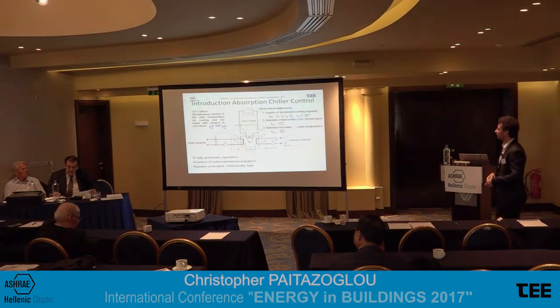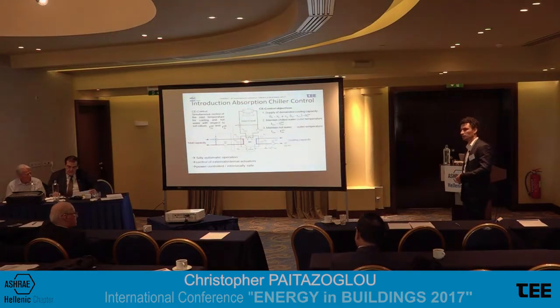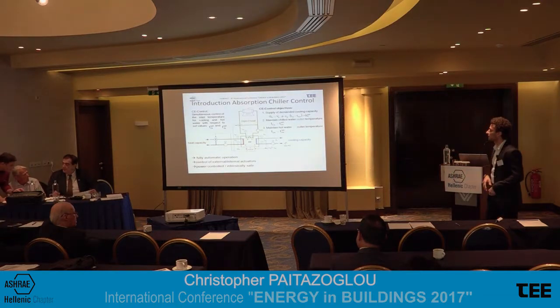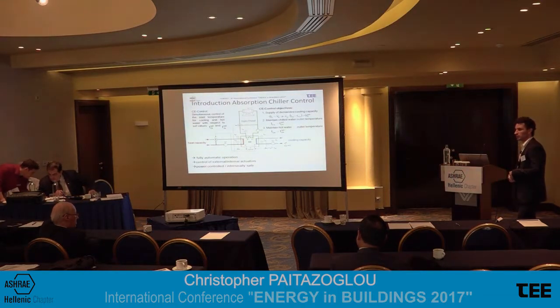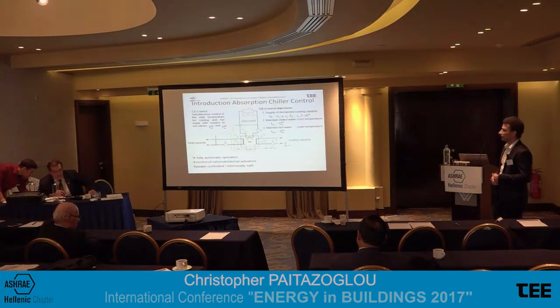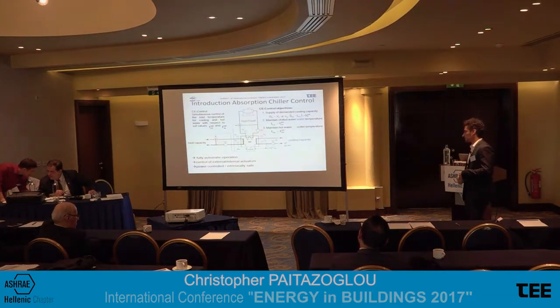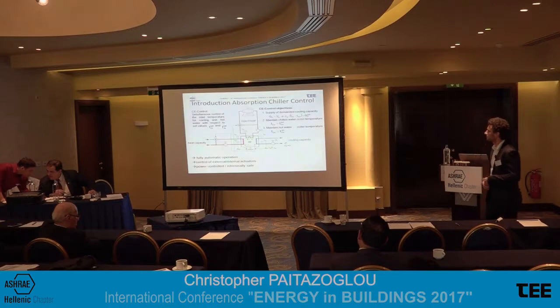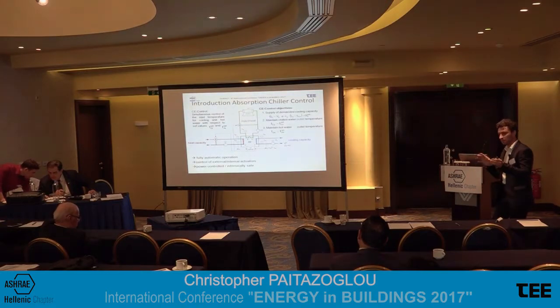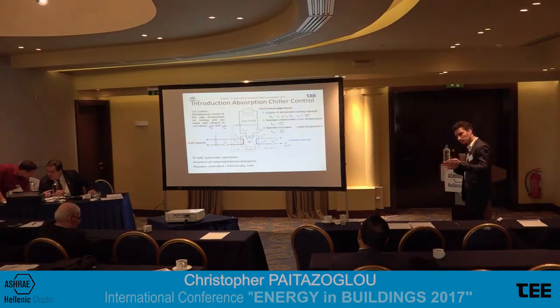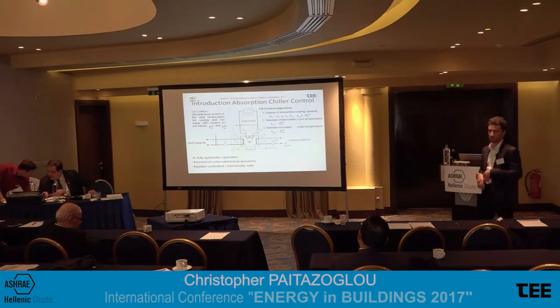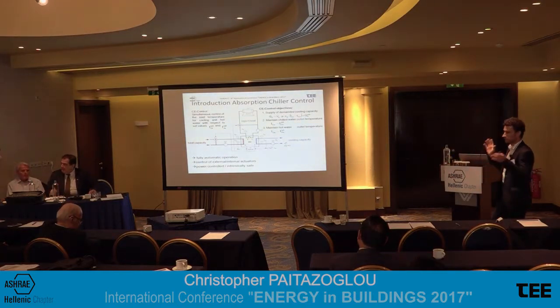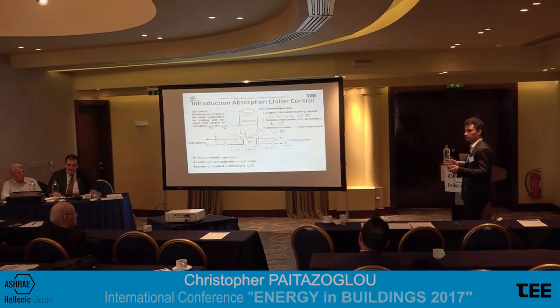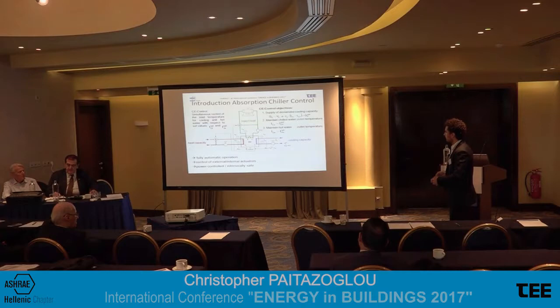Let's get over to the absorption chiller control that is implemented in the field test. This is based upon the CE control. This is the characteristic equation system, which has been developed by Professor Ziegler. And this takes into account that there is a characteristic temperature difference that can be applied to every heat pump in the market. And by knowing the external temperatures and the construction of the chiller, one can easily say at what temperature the chiller has to be driven in order to supply the cooling load.